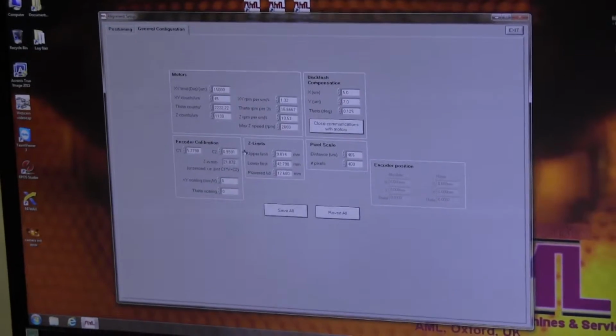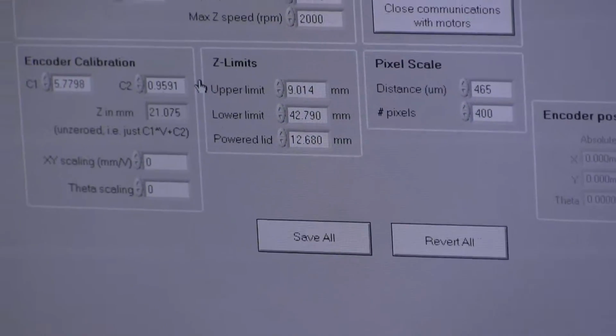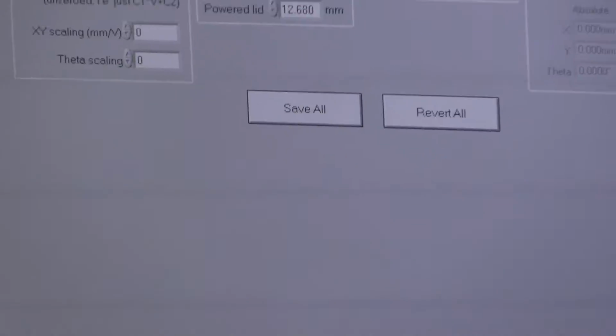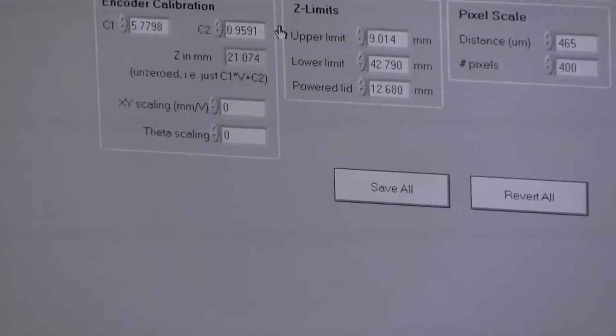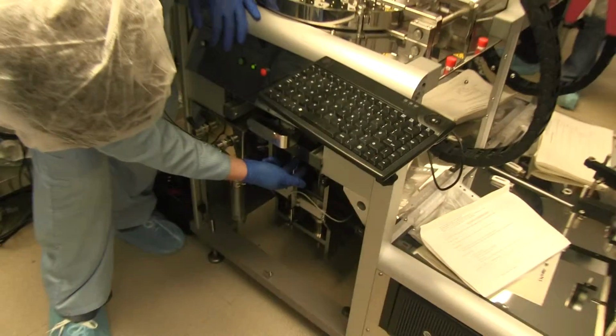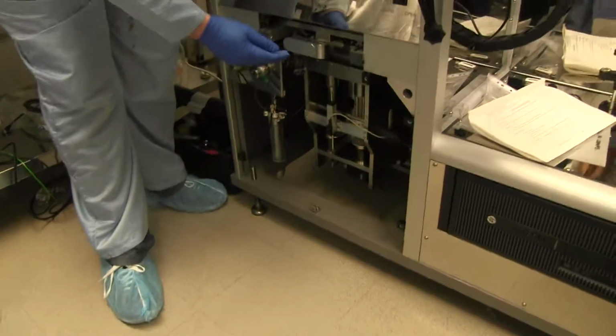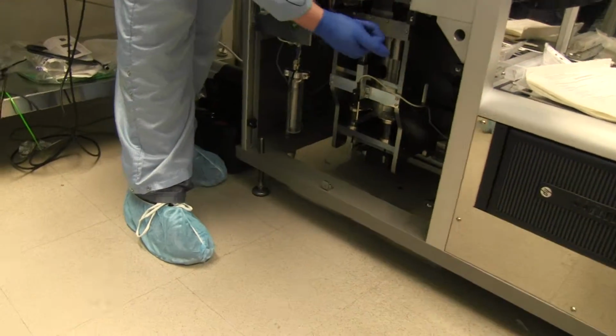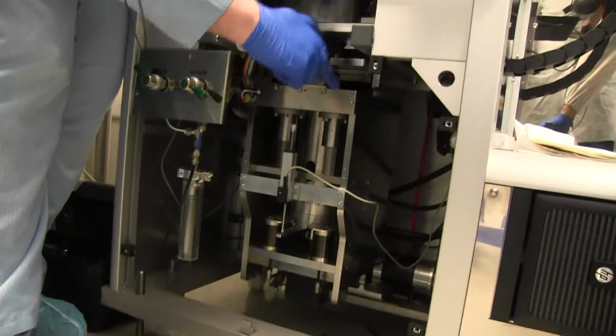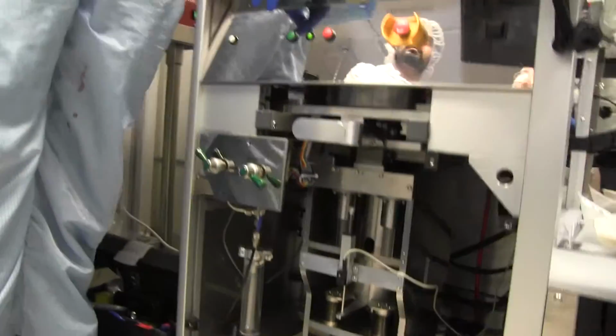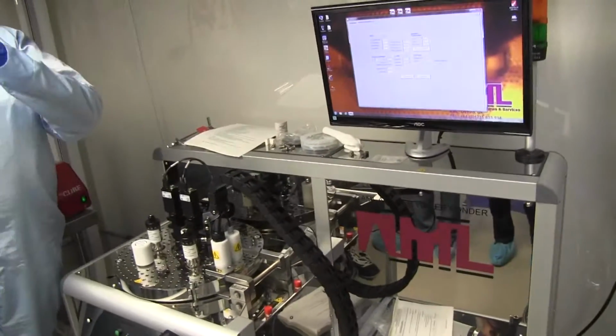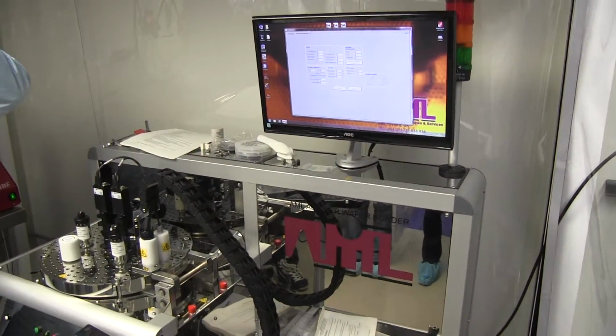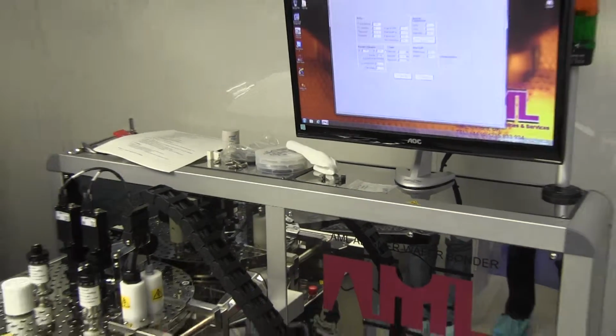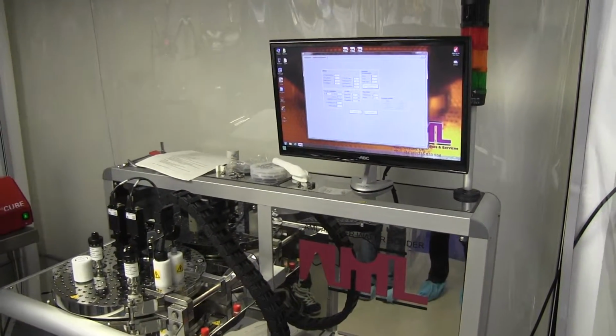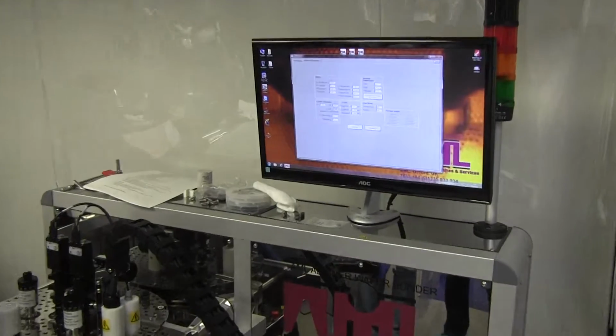Z limits, these are important. We don't want you to adjust these. So the upper limit is set to prevent mechanical clashing of any parts of the manipulator. So behind this brace bar here, there's a plate which is attached to these sliders, and the upper limit is when the plate underneath here collides with this plate at the top. So that value's been set with a feeler gauge. So at half a millimeter, when they're separated by half a millimeter, the software will stop the manipulator moving any further to prevent mechanical clashing, to protect the system.